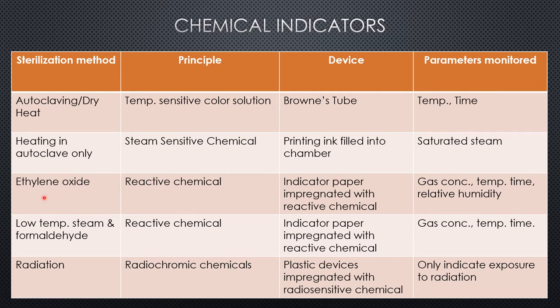For ethylene oxide gaseous sterilization, a reactive chemical indicator paper is used. This paper is impregnated with a reactive chemical which undergoes a distinct color change on reaction with ethylene oxide in the presence of heat. The color change occurs with heat, moisture, and gas. The parameters monitored are gas concentration, temperature, time, and relative humidity.